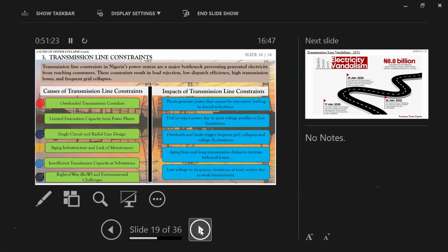Insufficient transformer capacity at substations, e.g., Aloji transmission station. Aloji NIPP power plant has the potential to supply over 1,000 megawatts. However, the substation has limited transformer capacity and poor interconnection with Aba and Owerri load centers. This leads to frequent load rejection by the DISCOs because TCN cannot evacuate power from Aloji efficiently. Then right of way and environmental challenges: transmission projects are often delayed due to land disputes, illegal structures, and forest encroachment.